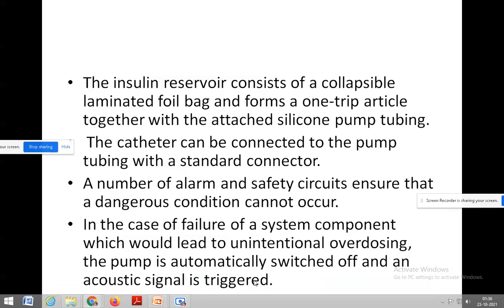So in case your device fails to work, what will happen? To avoid overdosing of insulin due to failure of the device, your pump will automatically switch off. When your device enters a failure condition, the pump automatically switches off and indicates it with a sound signal. That acoustic signal is nothing but a sound signal. An alarm will be produced in the case of failure.